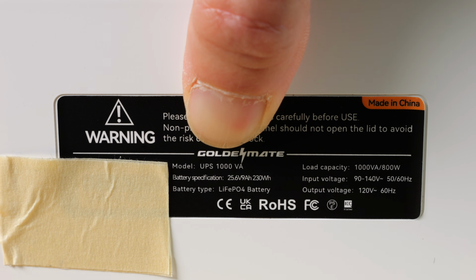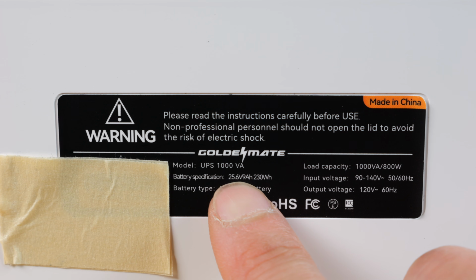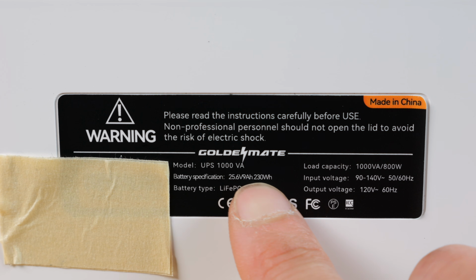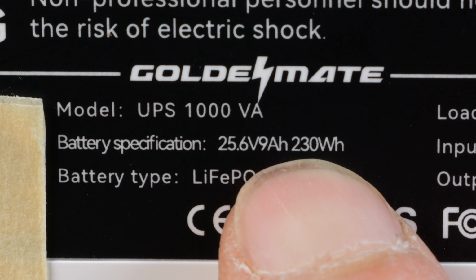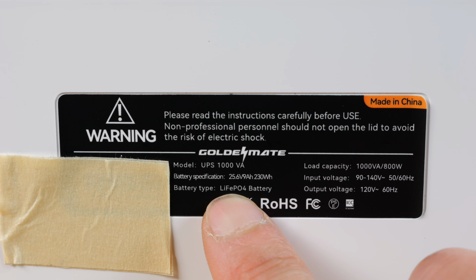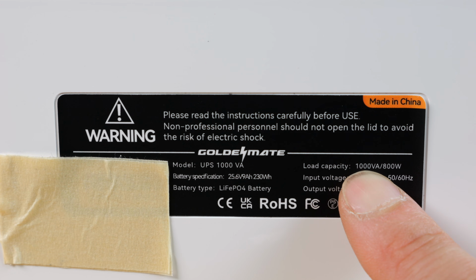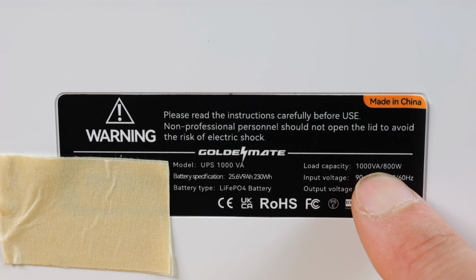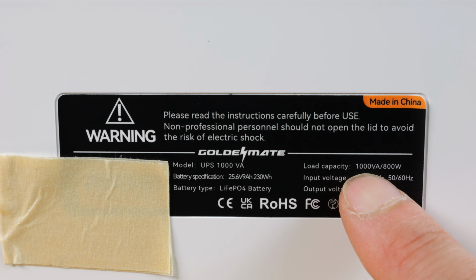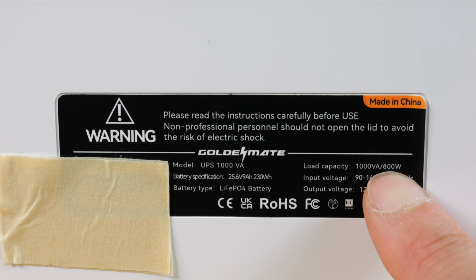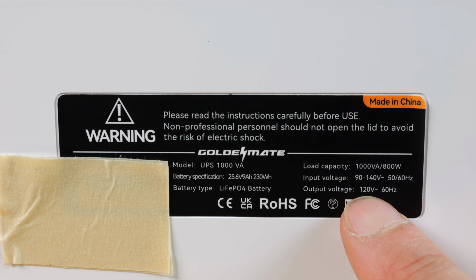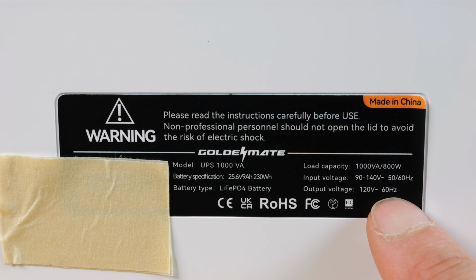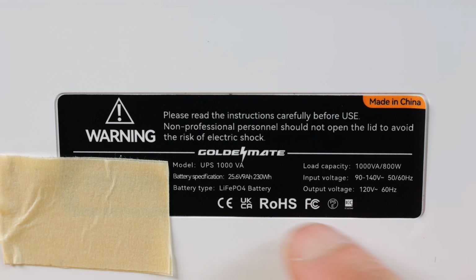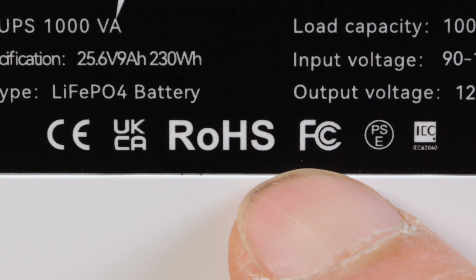UPS 1000 VA, 25.6 volts with 9 amp hours. This equates to 230 watt hours using a lithium iron phosphate battery. Load capacity is 1000 VA, which is voltage times amps, should be less than 1000 at all times. But in terms of wattage, it needs to be less than 800 watts. Output voltage 120 volts, 60 hertz. It has all the certifications, CE, RoHS, FCC.